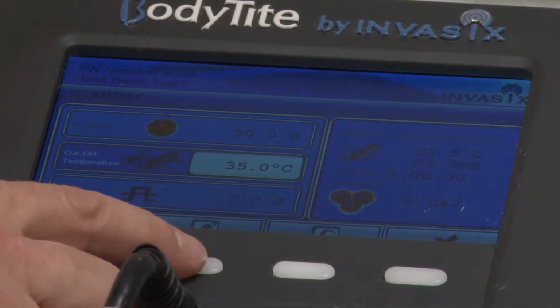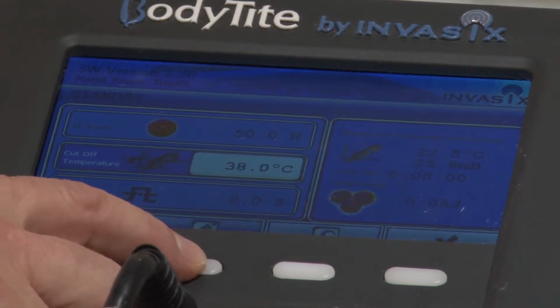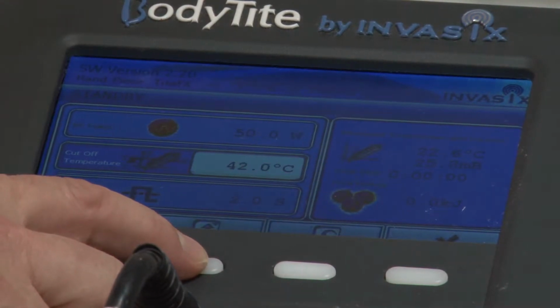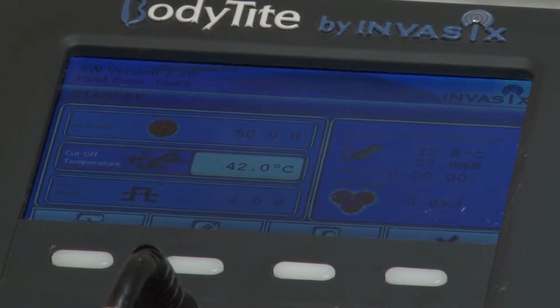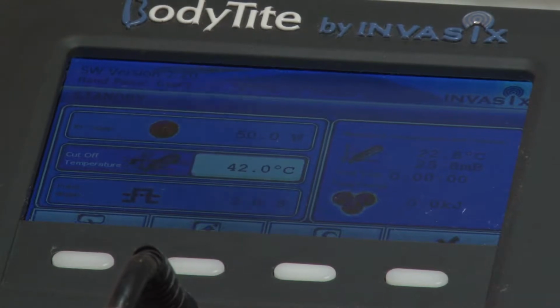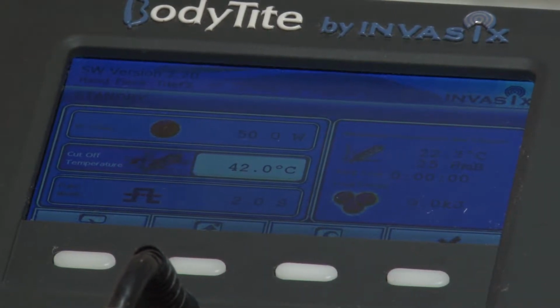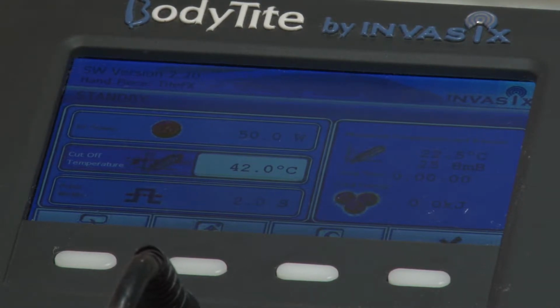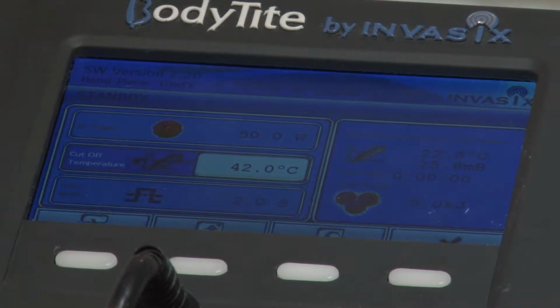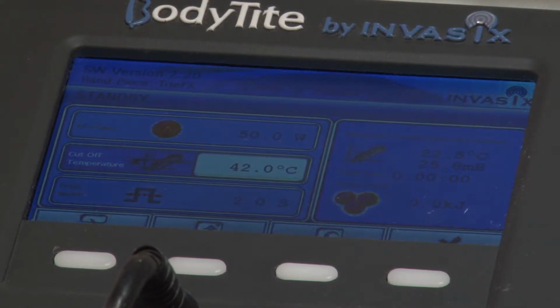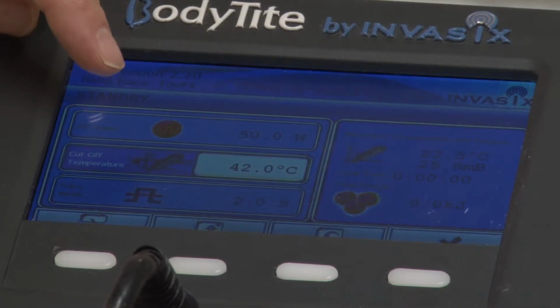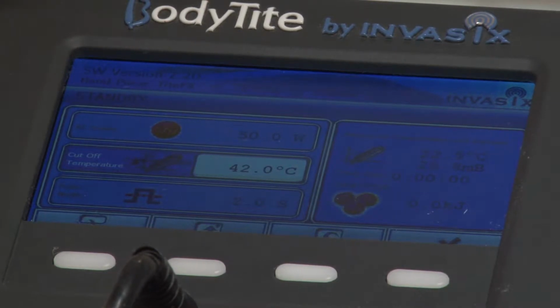The endpoint is usually 42 to 44 degrees, depending on what patients can tolerate. And so there's 42 degrees Celsius. When it gets to 42 degrees, it will turn off the RF. It will warn you 2 degrees prior to that with double beeping. So it's an auditory warning, thermally modulated basic RF system. When you get to your endpoint, it releases a second kind of RF, not the basic 1 million cycles per second RF that you get with most of the RF systems on the market, but a new type of RF.